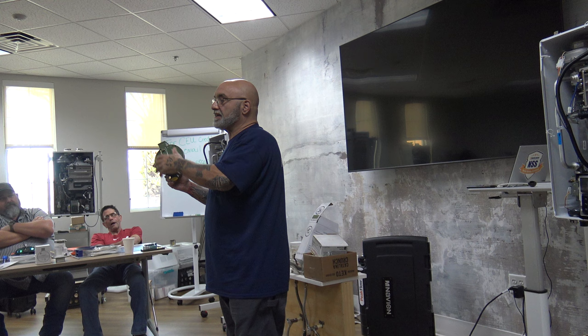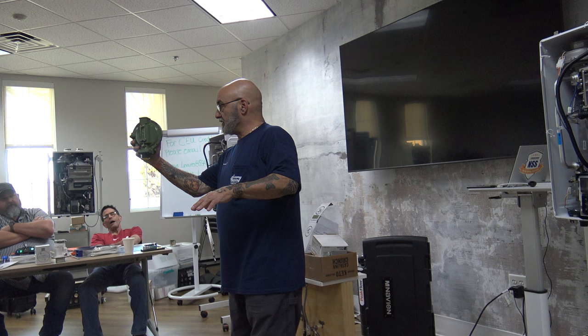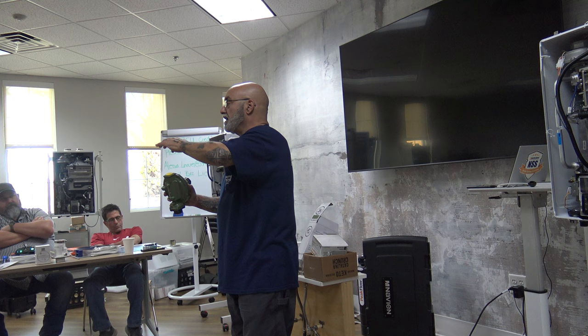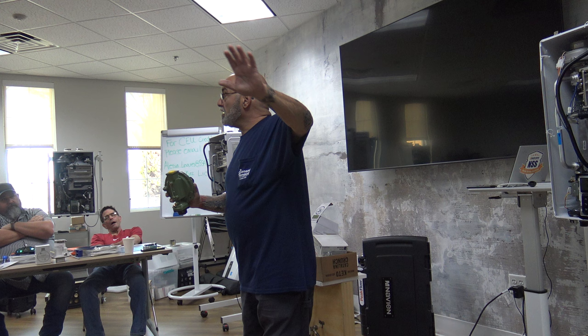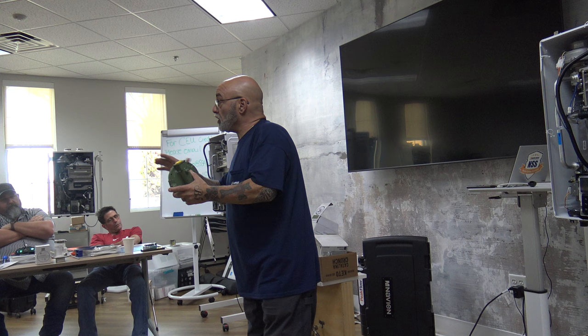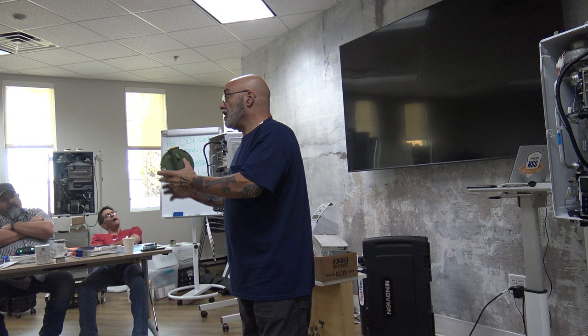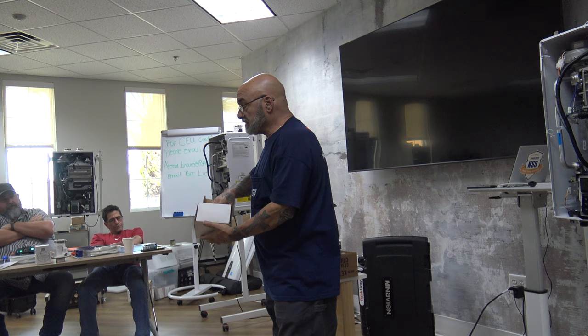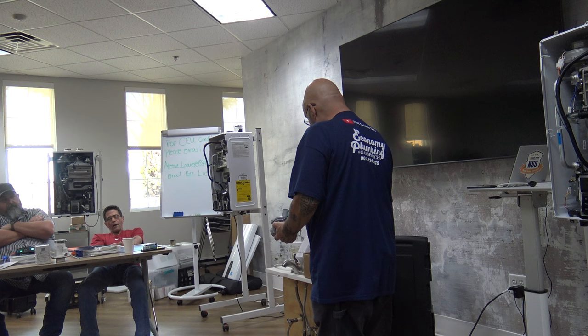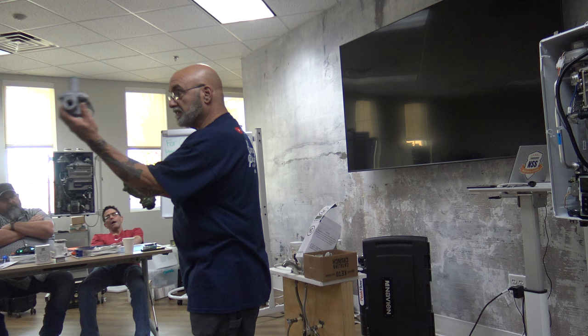So you've got 12 PSI coming in, and then you have this second stage regulator that reduces the 12 PSI to between 8 and 13 inches of water column. If you notice what was set up here, that's perfect for what you need. Then it comes in the house and goes to the appliance. You might have a 2 pound regulator that reduces it to 2 pounds, because you have 80 feet of gas pipe in the house, and then you're going to have a 2 pound to inches regulator, which is this Pietro Fiorentini. This regulator, as opposed to this one, is strictly for propane second stage. This one is good for natural gas and propane, reducing from 2 pounds to inches.